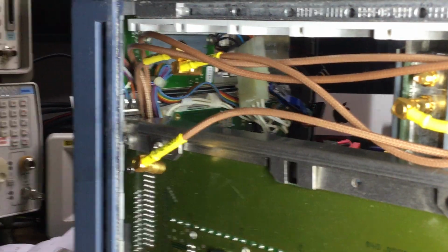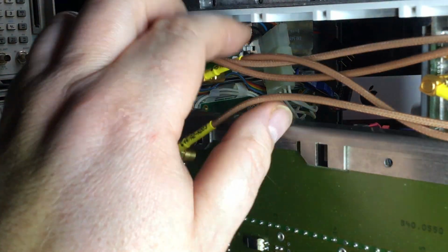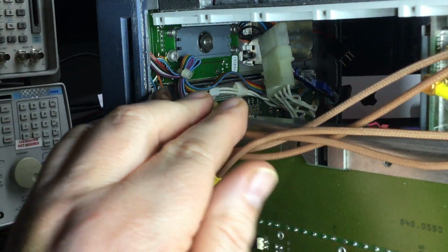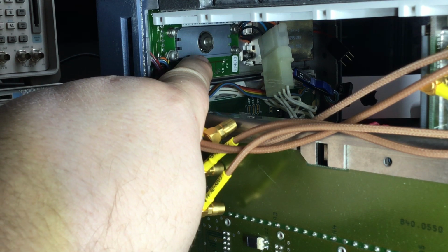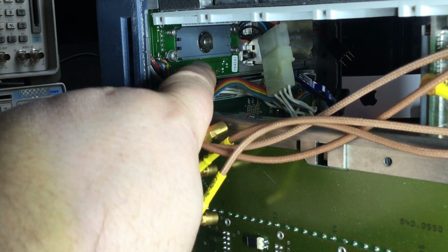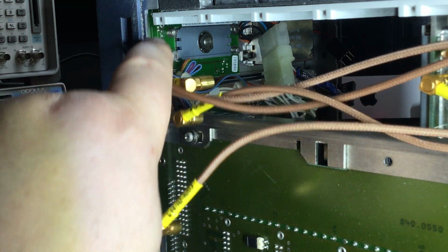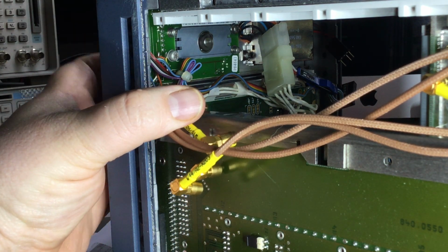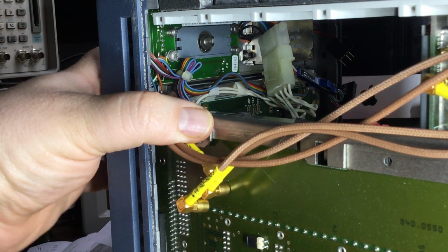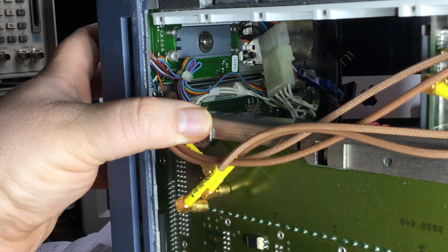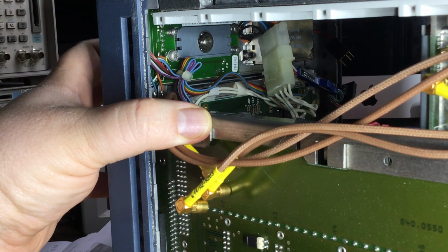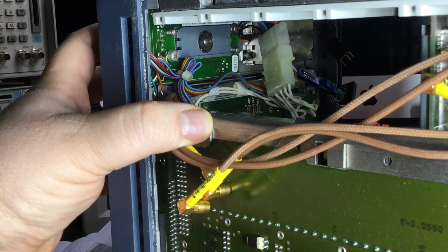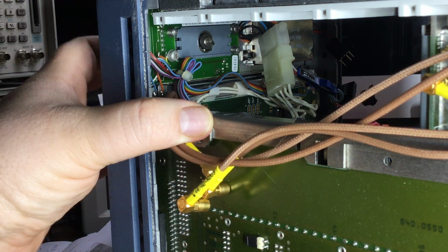Now as for the variable control, that's just under here. That's the control variable optical encoder or whatever, which we'll look at in the service manual. And if we turn the control, you'll be able to see the washer. I can see the ball bearing in it as well, which gives it its notch. There's an incremental notch feel to the control as you turn it. It's got these little notches in it like that, as you can see as you turn it, made up around the whole circumference of a turning circle.